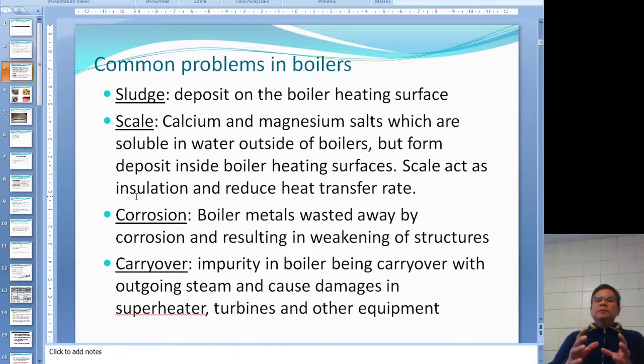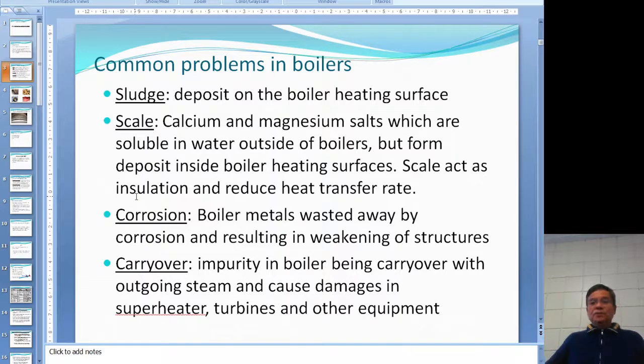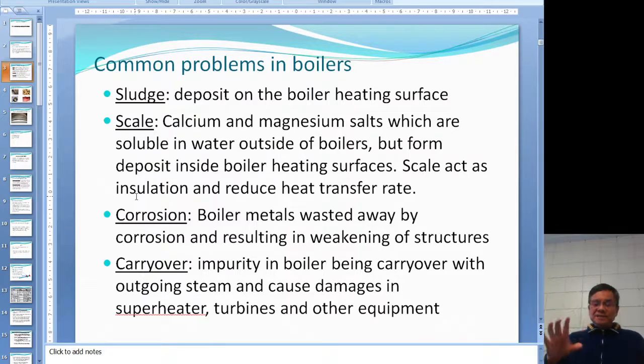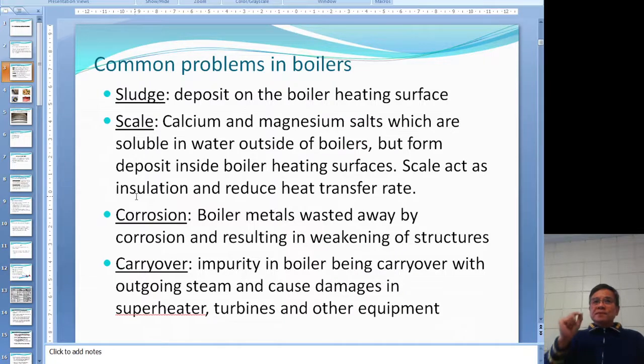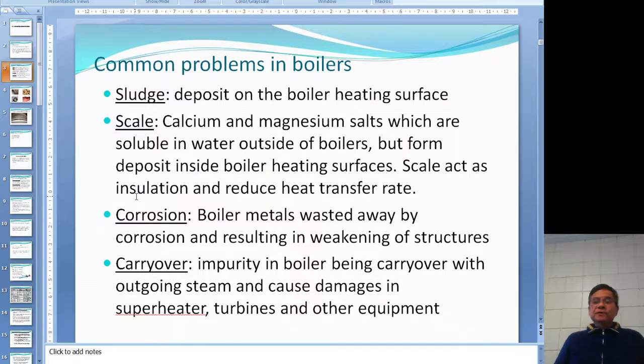The common problems in the boiler — we want the boiler to last as long as possible. There are two concerns: longevity and economy. Sludge deposit is related to economy: if you have sludge depositing on the boiler heating surface, the heat transfer rate is reduced and you lose money.